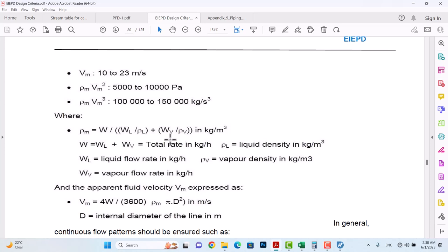Why? Because the oxygen velocity and the pressure drop changes for oxygen are extremely important. You know, oxygen is not simple. Oxygen is not like natural gas when there are some major pressure drop changes or changes in velocity. Sudden and abrupt changes in velocity, pressure drop or pressure of oxygen might lead to explosions. I have seen some of these explosions. It is really scary. Because of this experience and process demands, 12 inch was selected instead of 10 inch in order to relax the velocity.